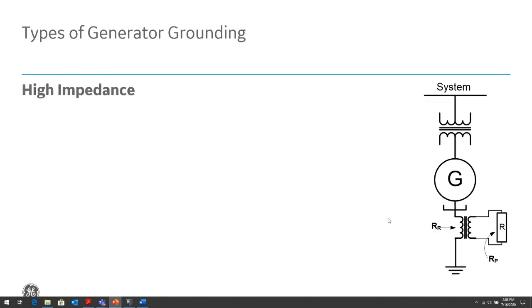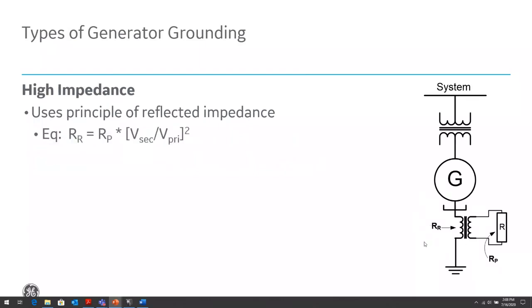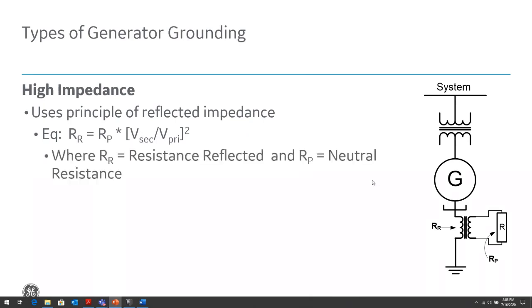The other type of grounding that we're going to talk about is the high impedance ground. There's a grounding CT in the generator ground path, which provides a high impedance to ground. It uses the principle of reflected impedance, where we reflect the primary impedance over to the secondary and hence have a high impedance to ground. The formula is: the reflected resistance is equal to the resistance in the ground circuit, RP, times the turn ratio of that transformer.